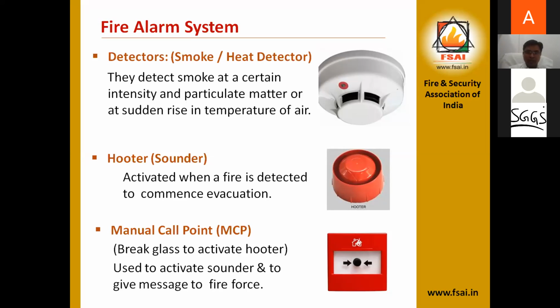Manual call point, means MCP. The break glass to activate the alarm. You can see in the figure, this unit is placed on the wall. So when any occupant finds that a fire has happened, he has to break the glass and push the switch so that the fire alarm panel is informed and everybody is alerted.